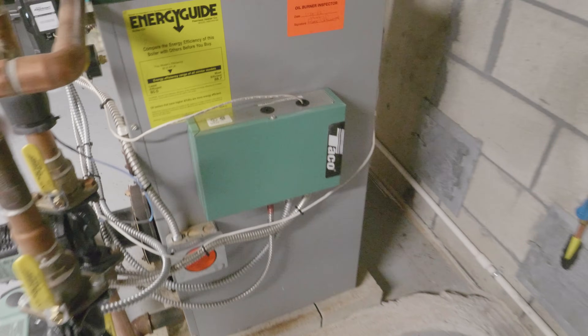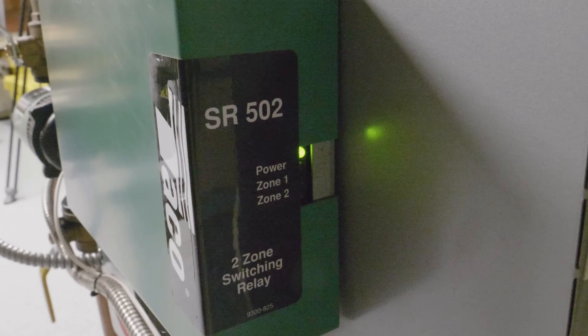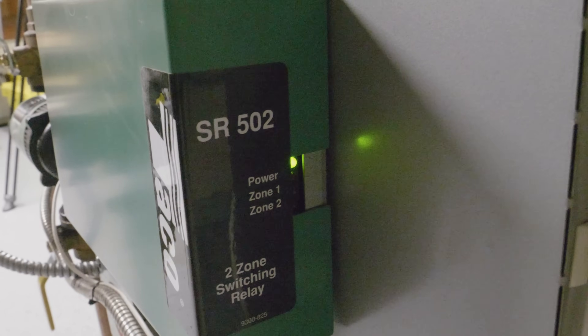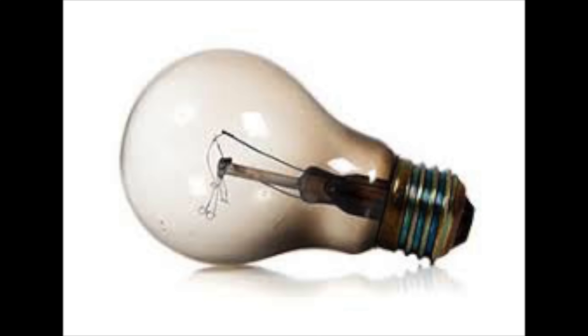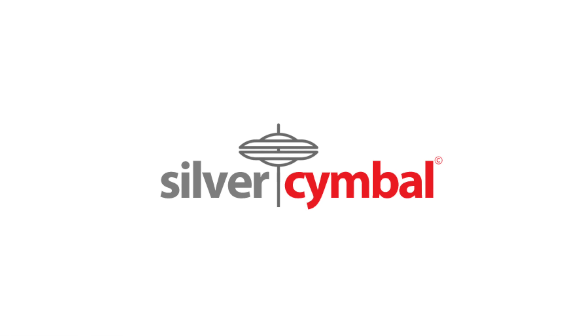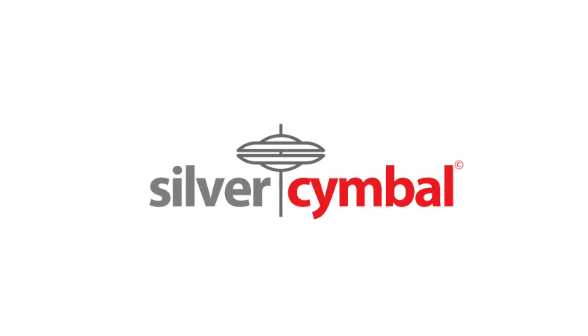The final thing to check is any electronics box on your boiler — this one says Taco on the side, but there are other brands. Look for any electronics and make sure there's at least a green light, an LCD, or some indication of electricity. If you have a box like this and there are no lights on at all when there should be, that could be another failure you'll need help to resolve. I hope this video was helpful — if it was, please give me a thumbs up, leave a comment below, and subscribe to my channel for more videos. Thanks for watching.